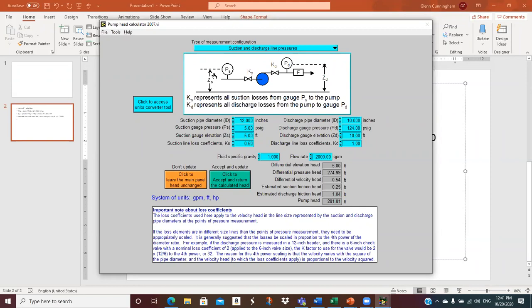For example, if the discharge pressure is measured in a 12-inch header, and there is a 6-inch check valve with a nominal loss coefficient of 2 applied to the 6-inch valve, the K factor used for the valve would be 2 times 12 over 6 to the fourth power, or 32. Oh, from 2 to 32. That could go up pretty quick. Oh my. The reason for this fourth power scaling is that the velocity varies with the square of the pipe diameter, and the velocity head to which the loss coefficient applies is proportional to the velocity squared. So you've got to be a little careful with that. But anyway, it depends on the configuration that you're working with. Okay, so that's that.